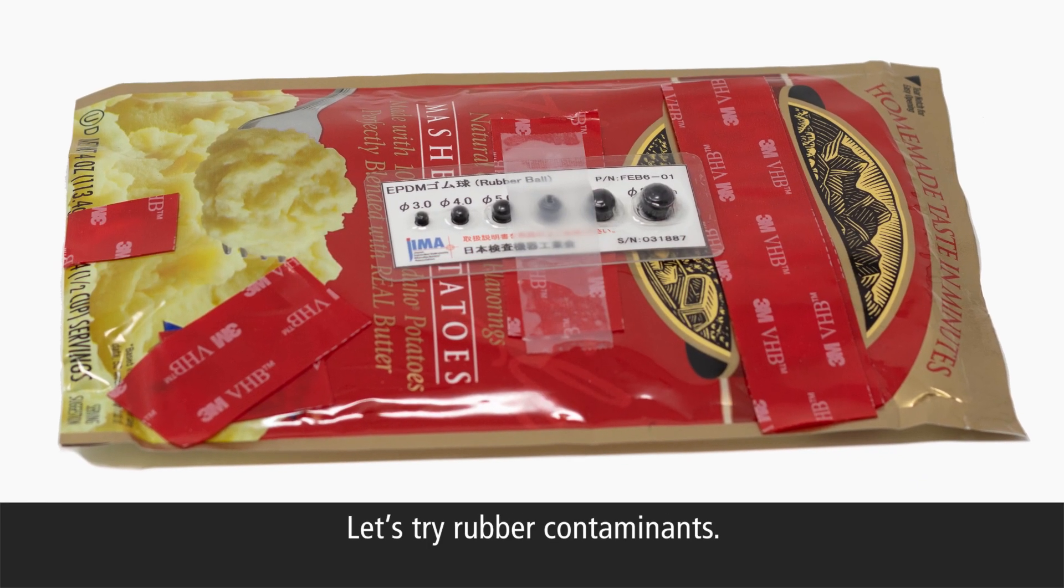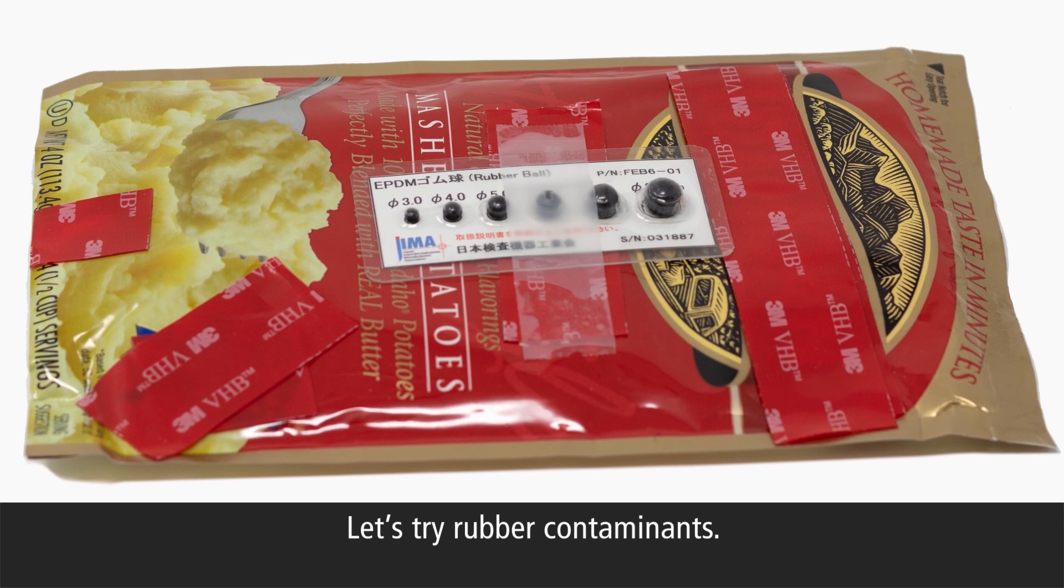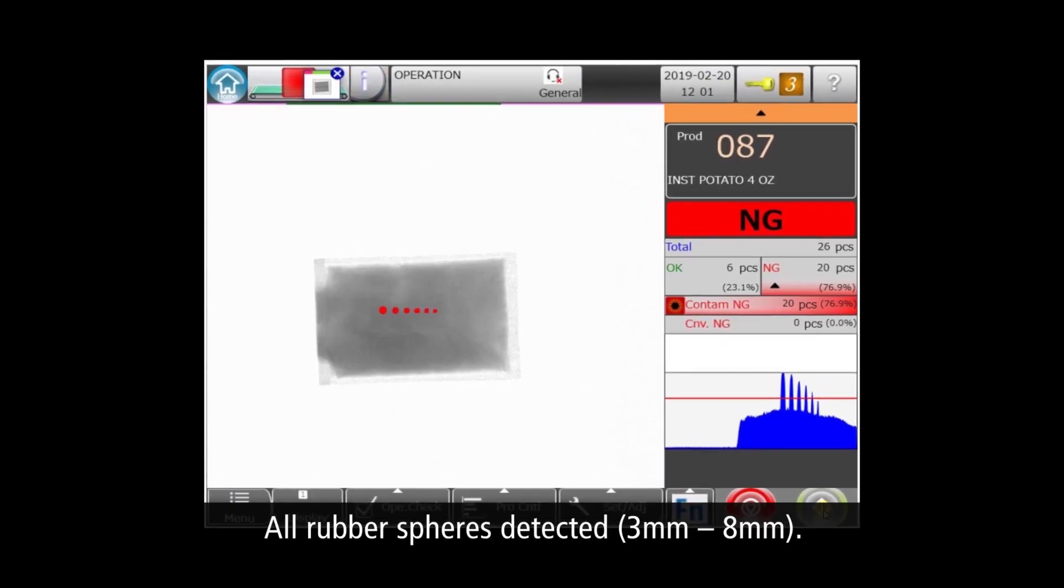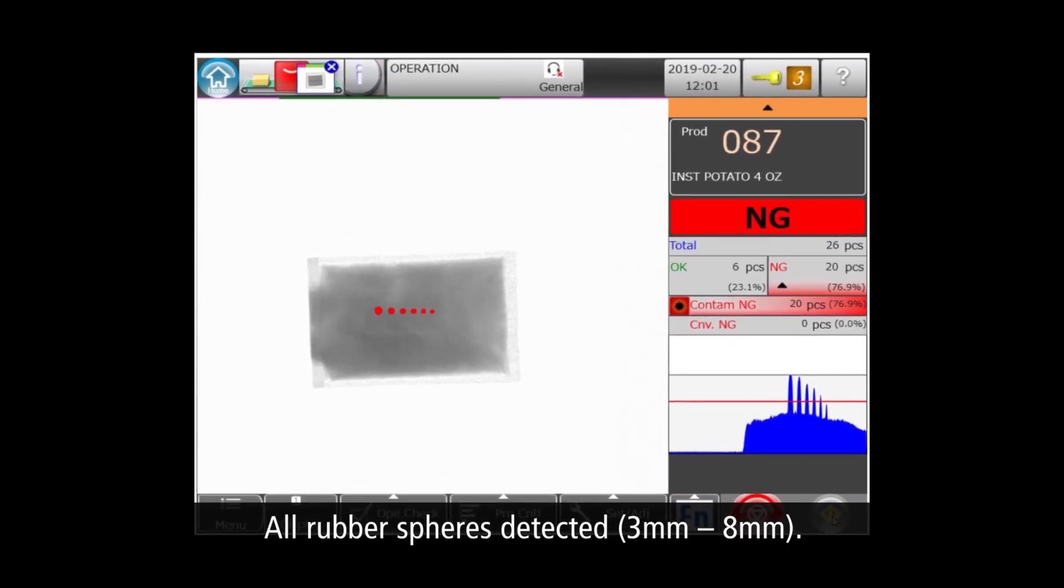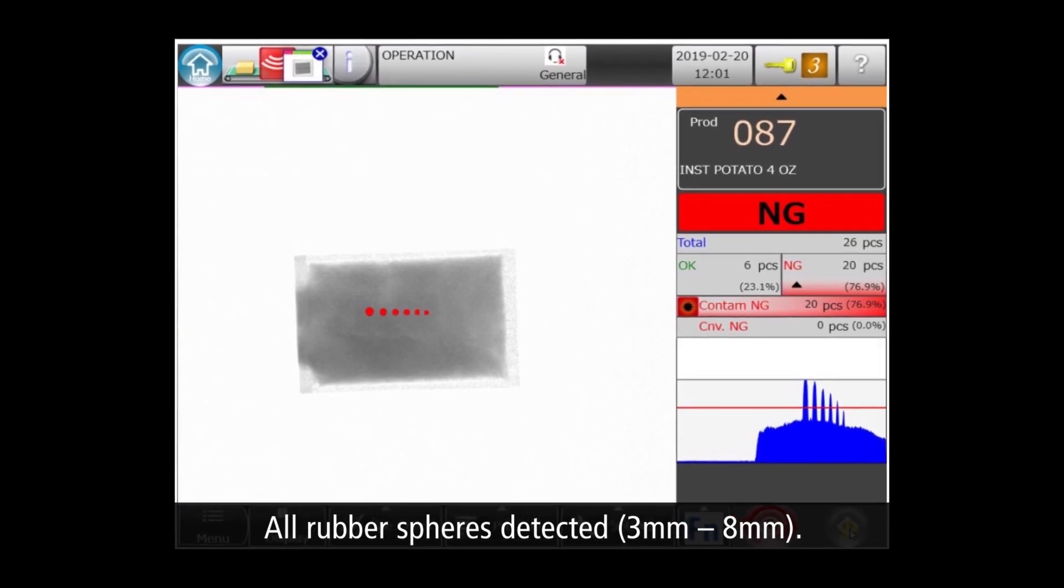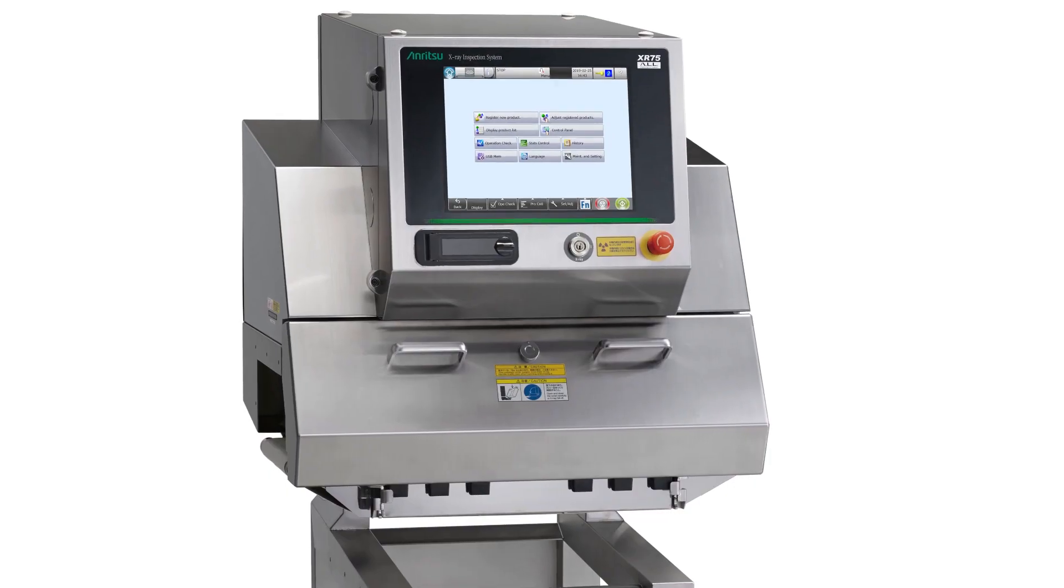Now let's try rubber, which is much harder to detect than steel due to its lower density. Once again, the machine found all six contaminant spheres, this time ranging from 3 to 8 millimeters.